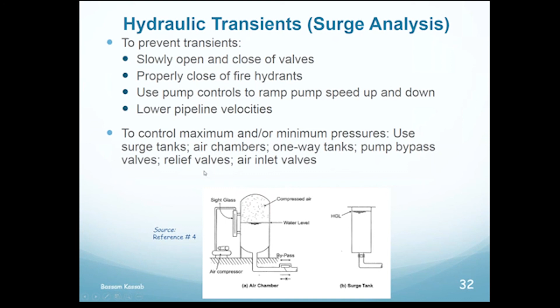But you can prevent that by slowly closing the valve, slowly closing a fire hydrant, and ramping up the speed of the pump. And design a network with small velocities, because with the high velocities, the transient will be more severe.